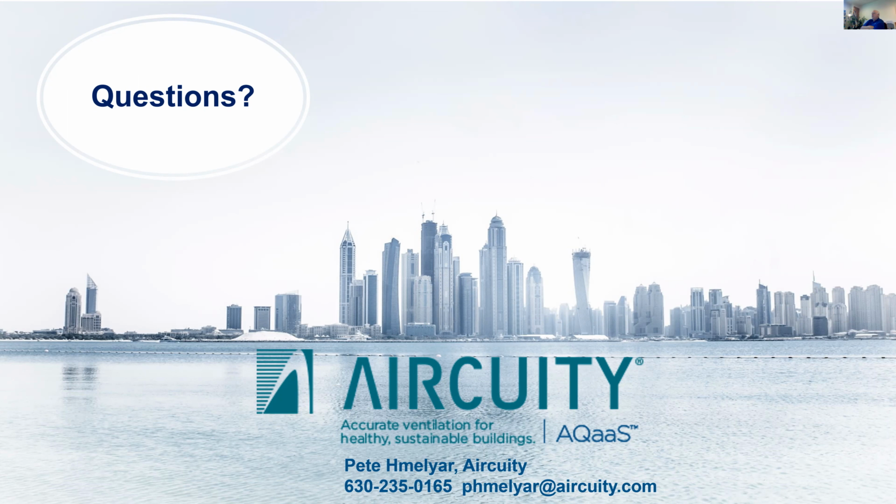There's a study that we can share, depending on what area you're at. We can send it to you from our local rep. It shows that we did some spill testing, spilling 200 milliliters of chemical, and looked at how long it took to react. It evaporates for a certain length of time, and because we react and go to such a higher air change rate, we make up for the fact that there could be a lag before we increase the ventilation air.